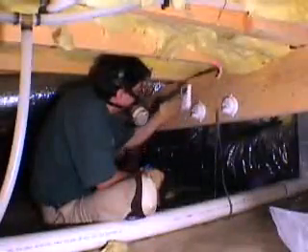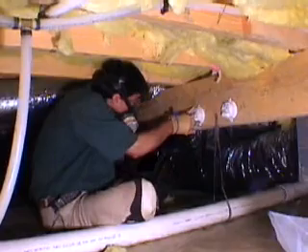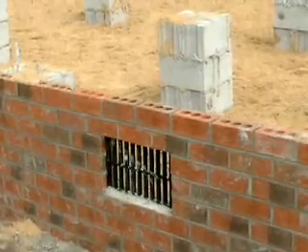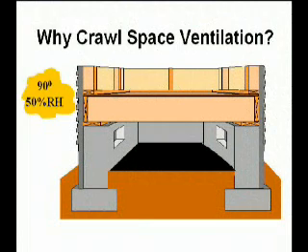Moisture conditions at the site are measured with data loggers that record temperature and relative humidity levels every 15 minutes. In wall-vented crawlspaces, foundation vents are installed to passively vent excess moisture to outdoors. This passive drying effect comes into question during the summer, when warm and humid outdoor air enters the crawlspace through the vents and adds moisture instead of removing moisture.